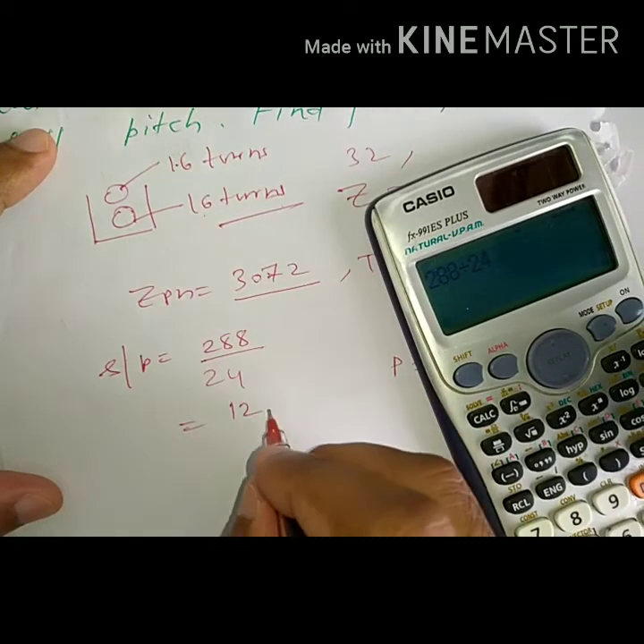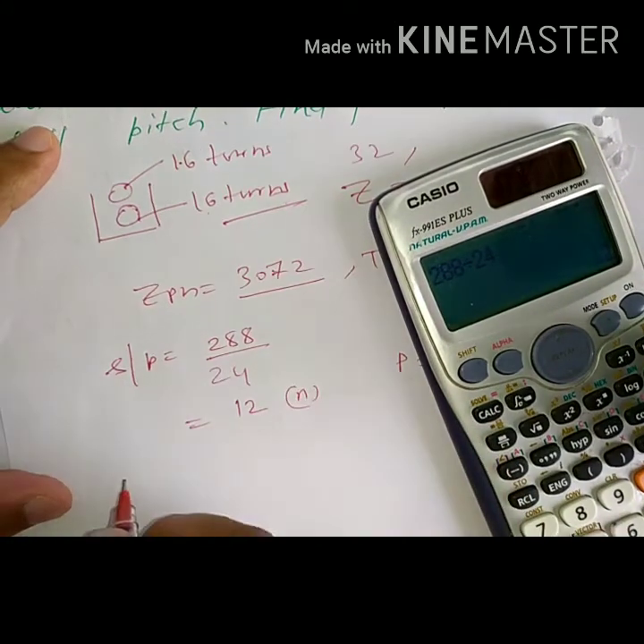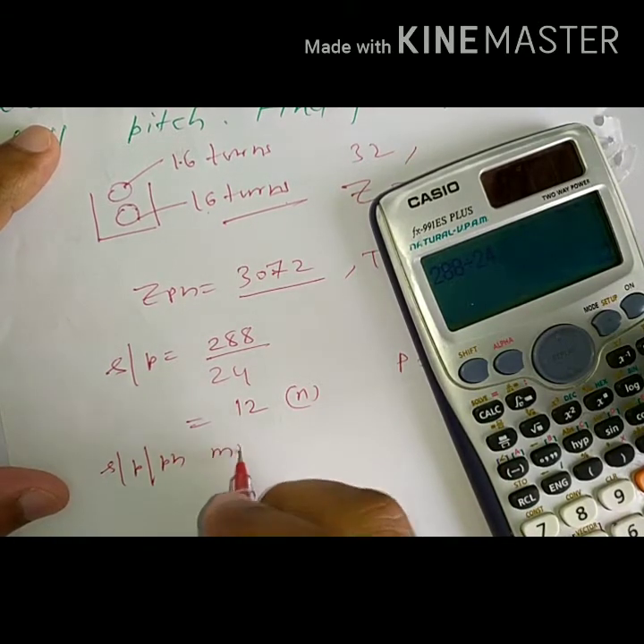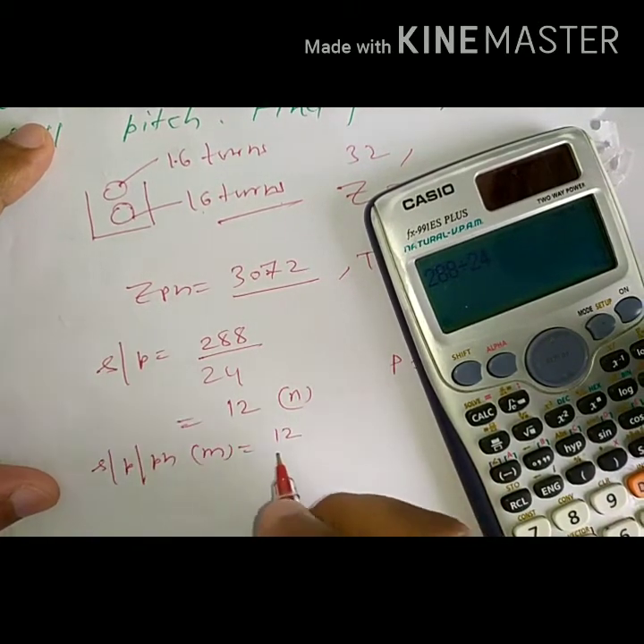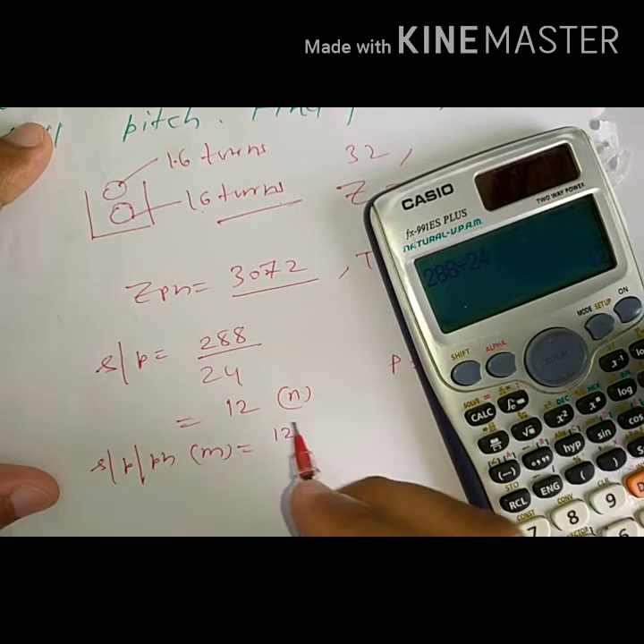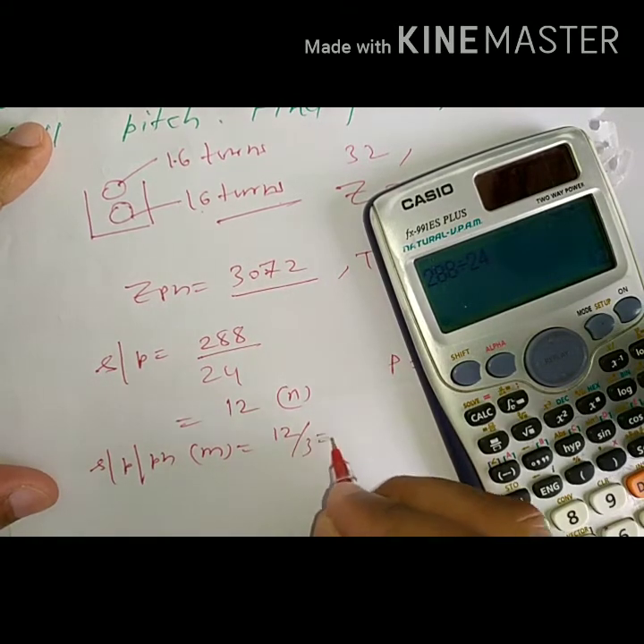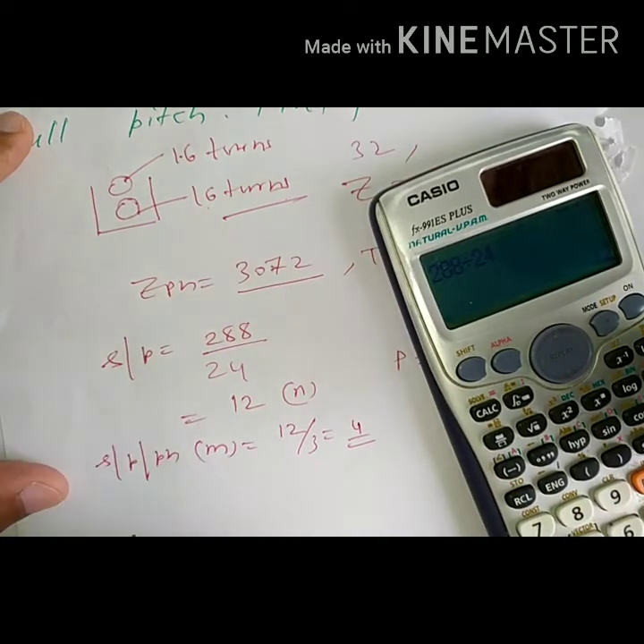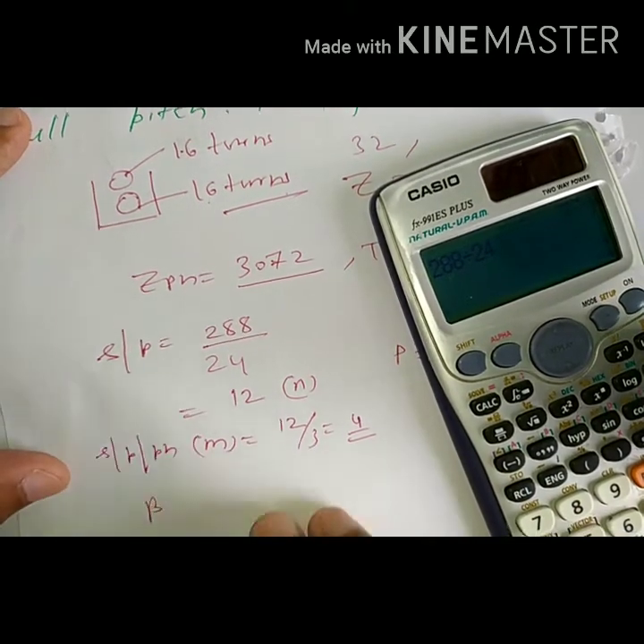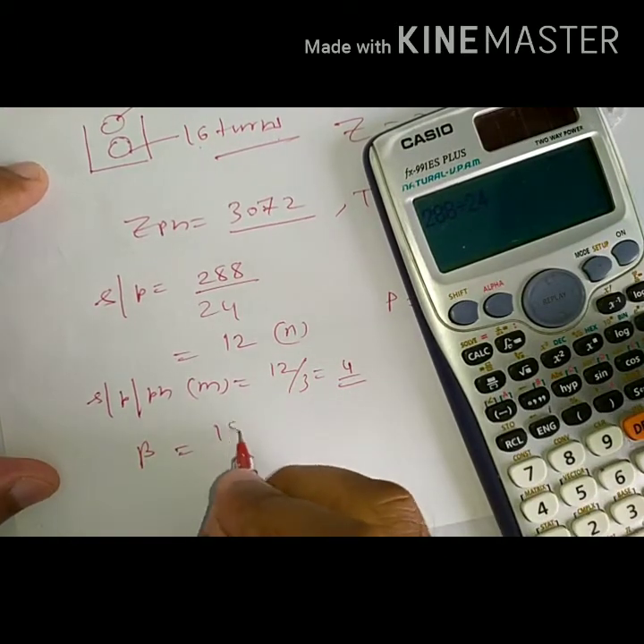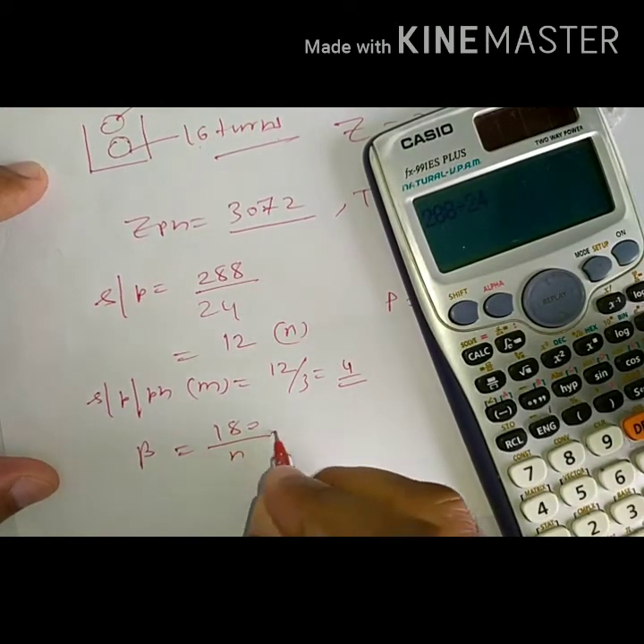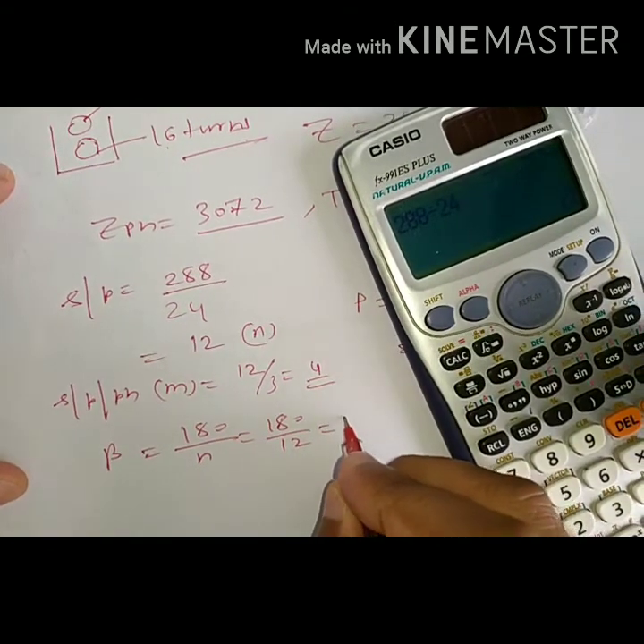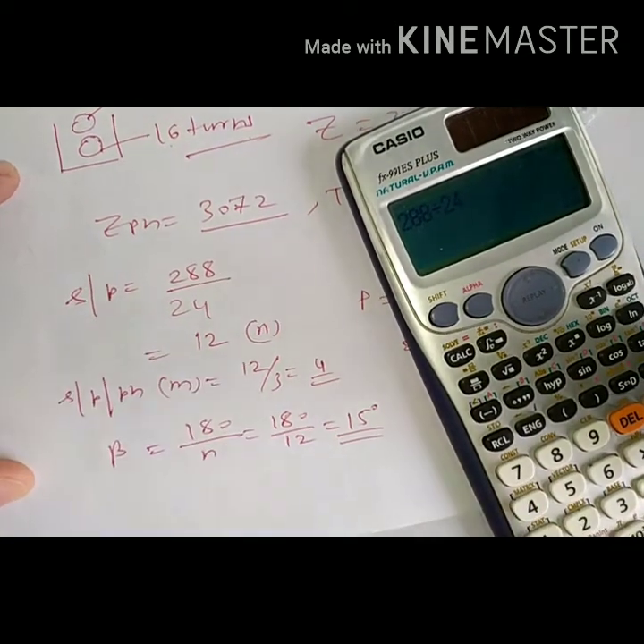Slots per pole per phase, that is m, equals slots per pole divided by number of phases = 12 divided by 3 = 4. Slot angle beta = 180 divided by slots per pole = 180 by 12 = 15 degrees.